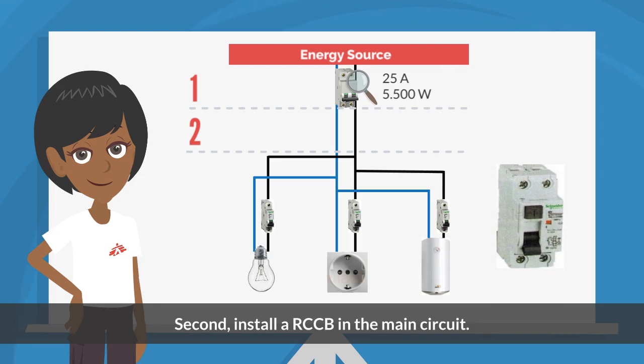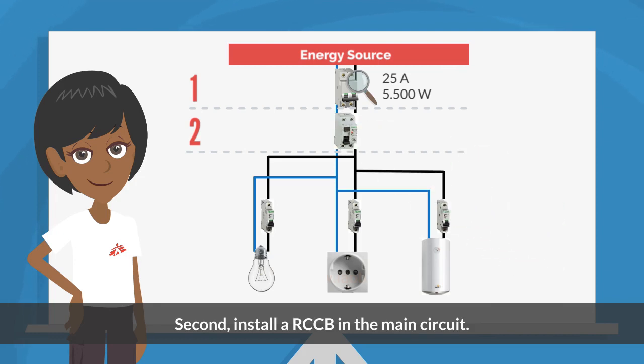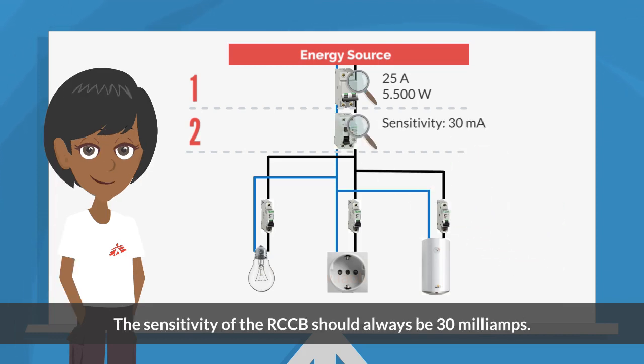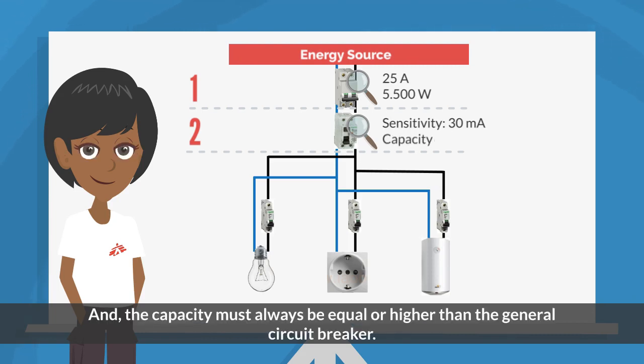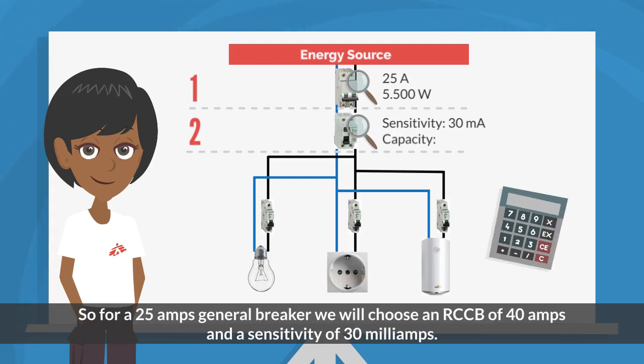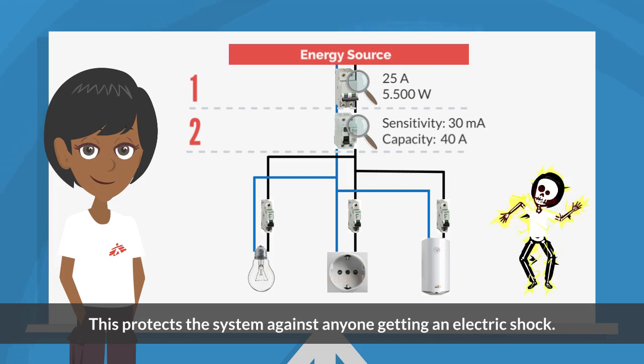Second, install a RCCB in the main circuit. The sensitivity of the RCCB should always be 30 mA. And the capacity must always be equal or higher than the general circuit breaker. So for a 25 amps general breaker we will choose an RCCB of 40 amps and a sensitivity of 30 mA. This protects the system against anyone getting an electric shock.